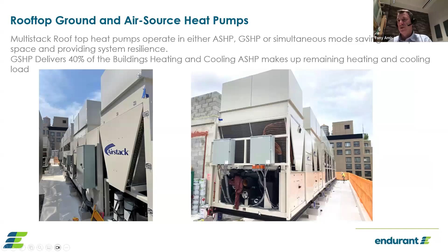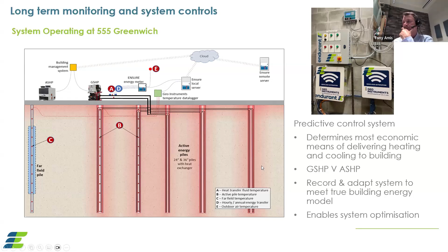So monitoring, as we've seen on Cerys's project, is a crucial component. It's crucially important to make sure you're monitoring what's going on with ground temperature. On this particular project, we had the opportunity to add in some strain gauges and temperature sensors through 3 piles, one a 24-inch pile, one a 36-inch pile, and one pile that was a 12-inch pile in the corner of the site that we didn't have any geothermal loops in. So we got a good idea of what the ground temperature was, where we weren't heating and cooling through the seasons. And now we've got about 18 months of data.